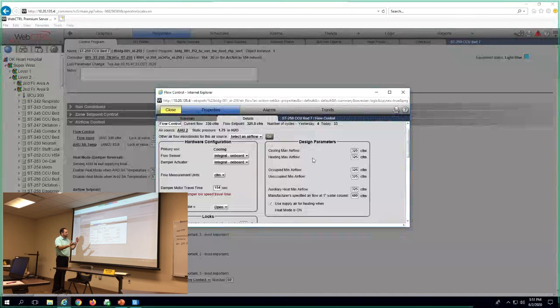Cooling max airflow, heating max airflow, occupied min, unoccupied min, auxiliary heat min, and then dampers, or manufacturer specified airflow at 1 inch water column. This number right here, don't ever change it, because this is already set. Everybody, we did it when we calibrated them. We took the manufacturer's data, said what it's going to be at 1 inch, and then our TAB guys adjusted or calibrated the VAV boxes, right?